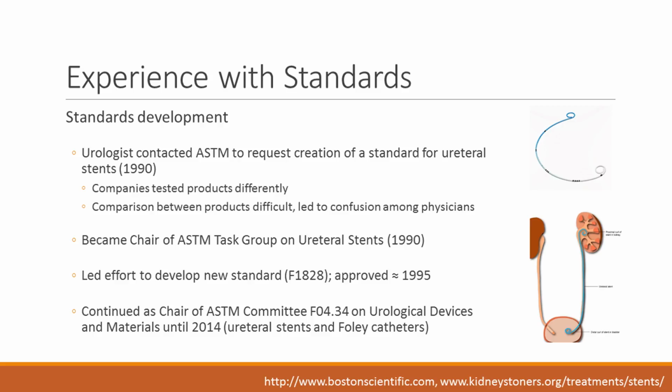So there were about 5 or 6 companies that made ureteral stents, and this urologist was concerned because every company seemed to test their ureteral stents differently, which made comparison between products very difficult because you couldn't compare apples to apples because different test procedures were being used. And it led to some confusion. Companies were measuring the lengths differently. So he said, you know, we need a standard.